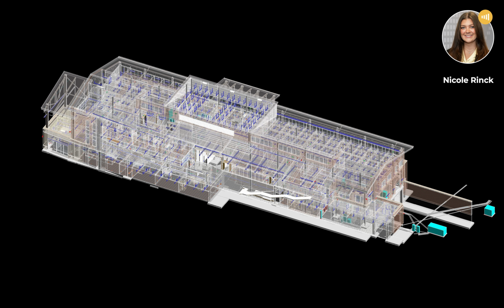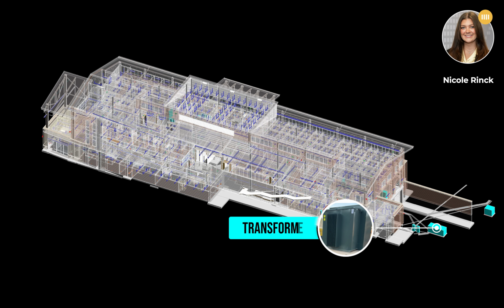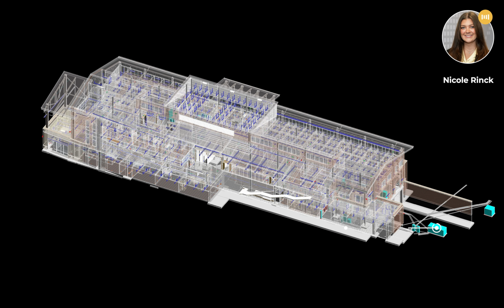The electrical system in a building is very vital to occupant comfort, and it provides power to the mechanical and plumbing systems, lighting systems, appliances, and any visual displays. First, you must determine where on site your power is coming from. The utility provides power to the building, and then this power enters a transformer. This transformer is typically located at the exterior of the building, and its purpose is to step the voltage down to a voltage that is usable by the large equipment in the building.